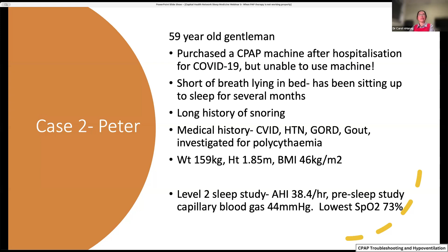So I persuaded Peter to use his own APAP machine, on the setting that he had been set up for. And he came back after months and told me that he had no improvement in symptoms. Let's have a look and see what his machine is doing for him. Again, this is a 1 month download, and his machine is set to have a minimum of 6 centimeters water and a maximum of 20 centimeters water. And again, they've put a ramp of 20 minutes to allow him to fall asleep.